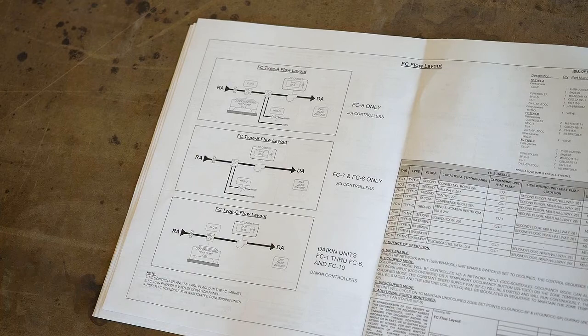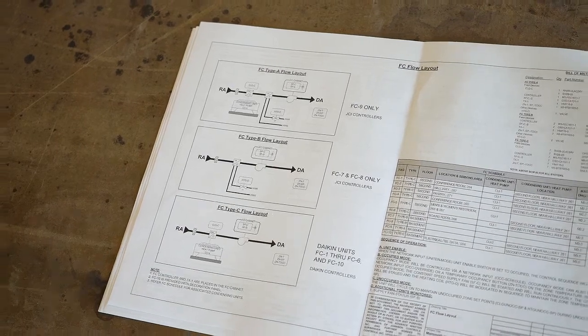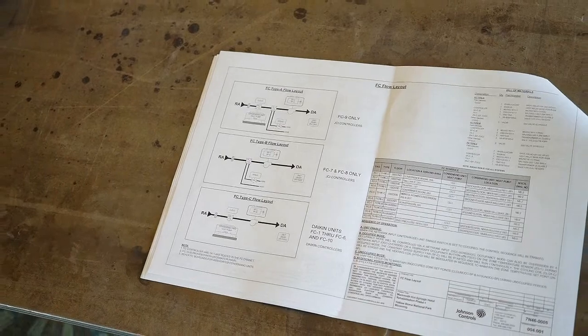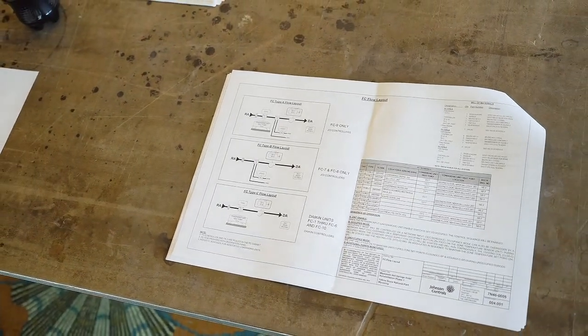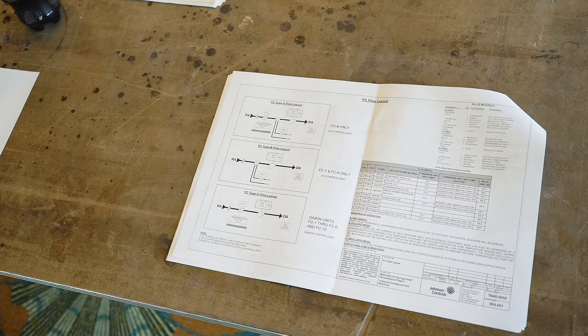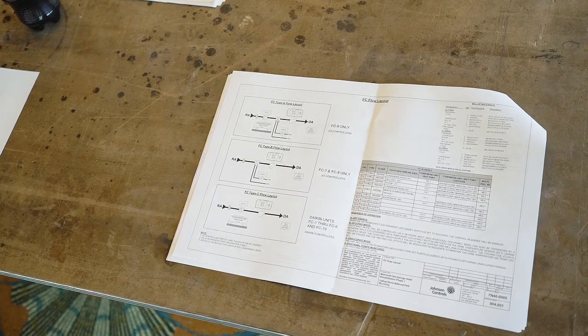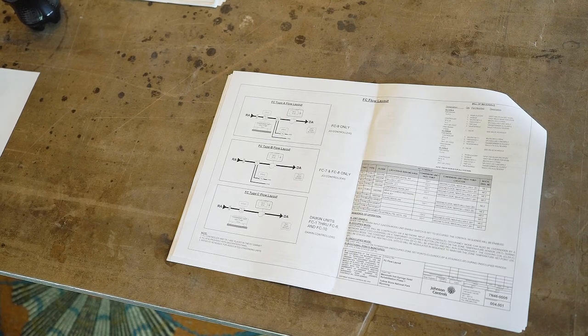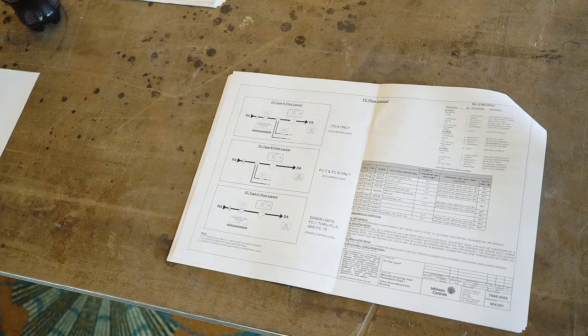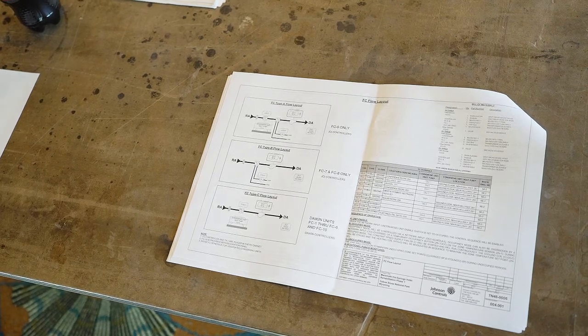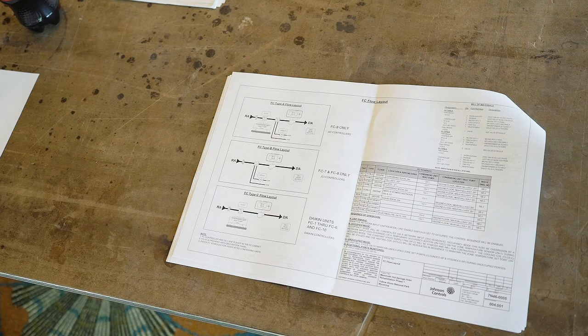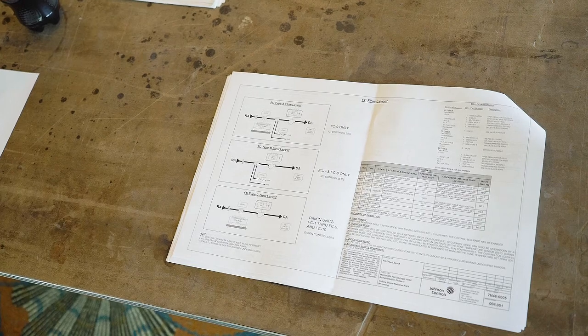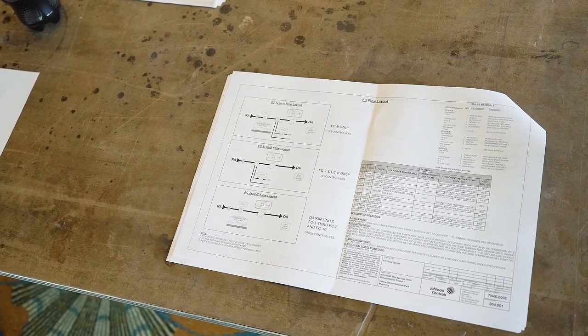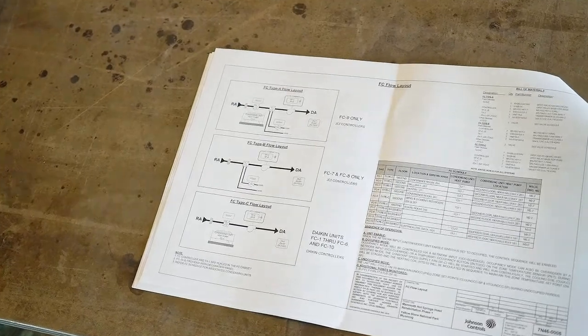Okay? So what that allows us to do is to plug in a Cat5 cable, and then we're able to pull it through your network and pull it onto our front end to see the points that are available. So zone temperature set points, stuff like that on the Daikin units. We can see status on the indoor fans to see if they're running, and we can see if the condensing units outside are active or inactive. Okay, again, we're not commanding any of that, we're just monitoring. Okay, so that's how the units are wired.